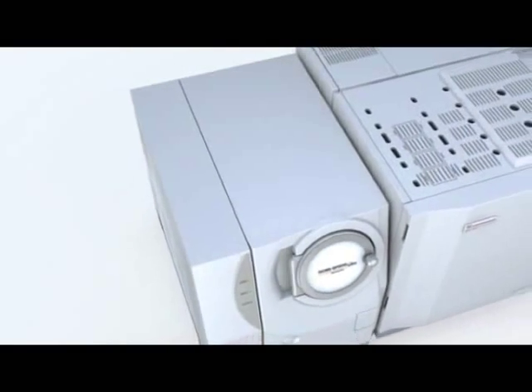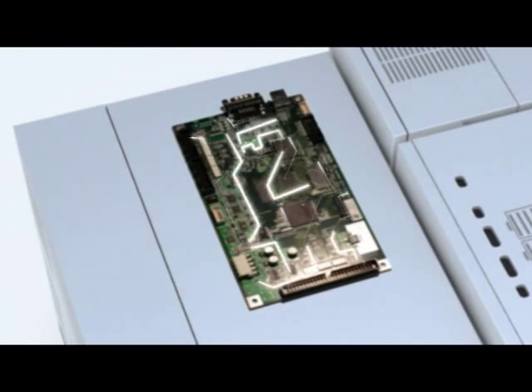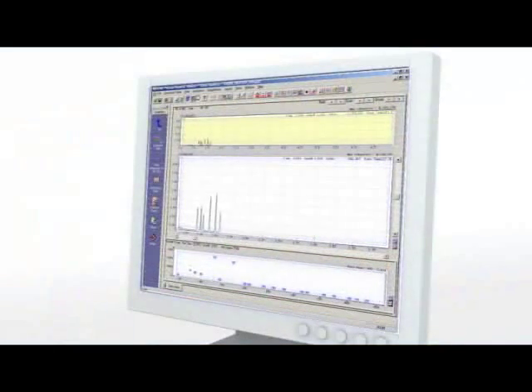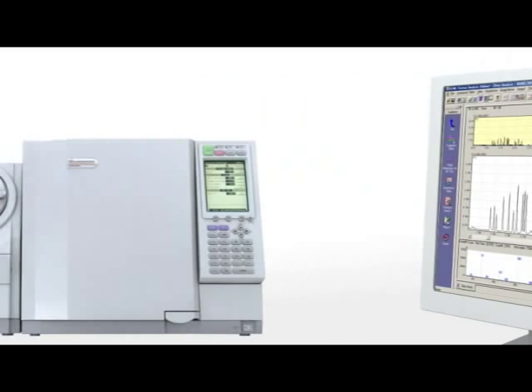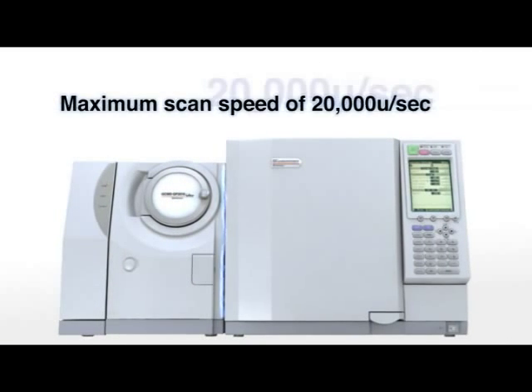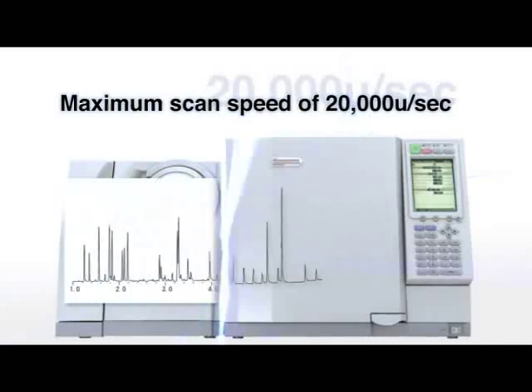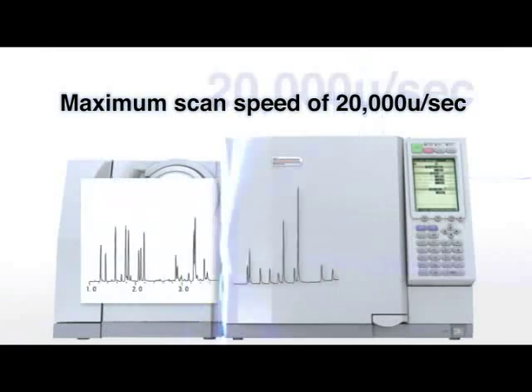ASSP is a firmware protocol that optimizes the ion transmission hardware parameters with a highly efficient data collection algorithm, allowing high mass spectrometer scanning speed and data collection. This achieves maximum data acquisition speeds of 20,000 AMU per second and results in a level of sensitivity more than five times better than that of older instruments.